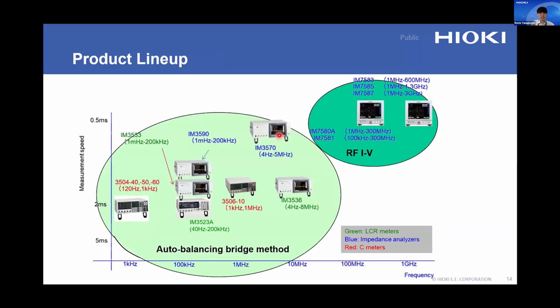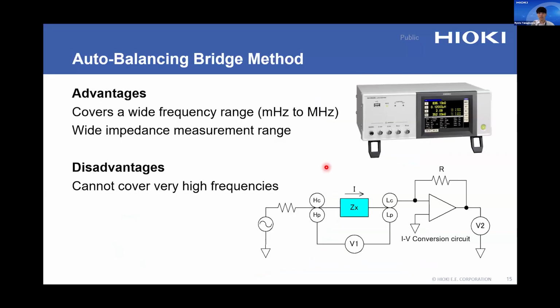Now, to measure impedance, we offer the following product lineup. There are two main measurement methods. One is the auto-balancing bridge method, which covers a wide frequency range, and the other is the RF-IV method, which is specialized for high frequency measurement. Since each method has different characteristics, I will explain them one by one. Okay, first let's look at the auto-balancing bridge method. This method is used in our IM35 series as well as LCR meters such as the 3504 and 3506.